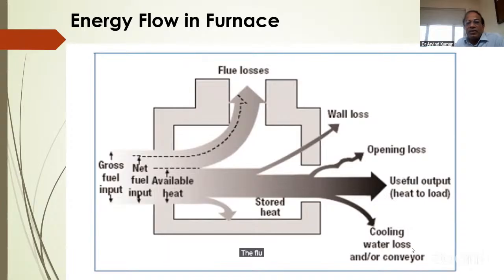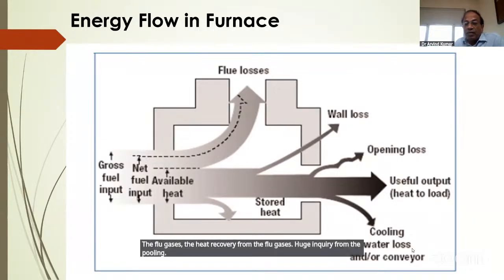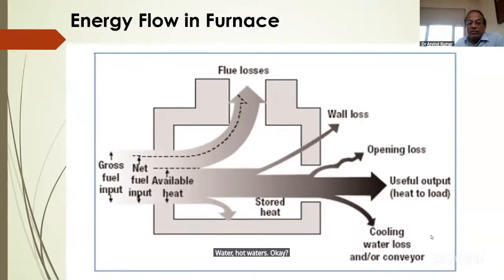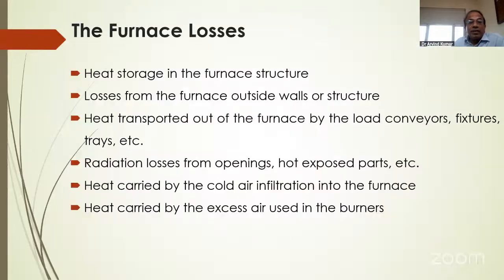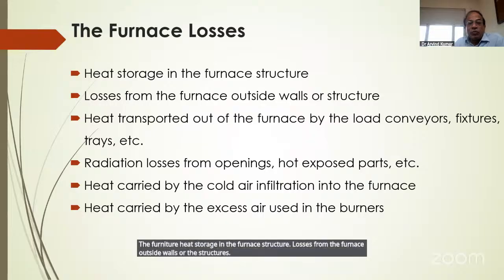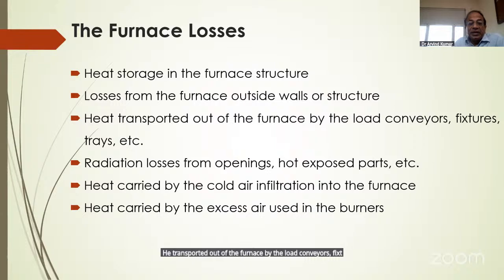The heat recovery from the flue gases, and heat recovery from the cooling water and hot water. Minimum heat should be stored in the furnace. The furnace is designed, or the load is placed in the furnace, so that the maximum energy is utilized, so it depends upon the design of the furnace. Losses include heat storage in the furnace structure, losses from the furnace outside walls or structures, heat transported out of the furnace by the load conveyors, fixtures, and trays, radiation losses from openings and hot exposed parts, heat carried away by cold air infiltration into the furnace, and heat carried away by the excess air used in the burners.